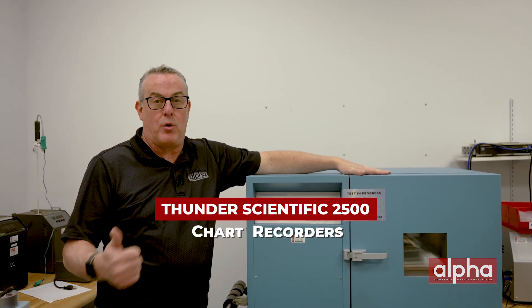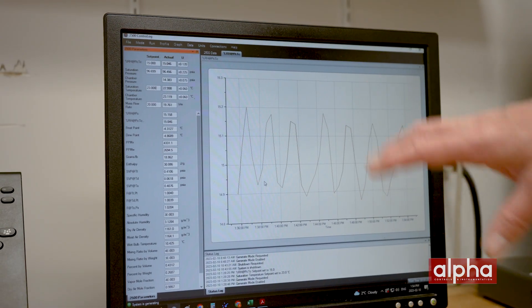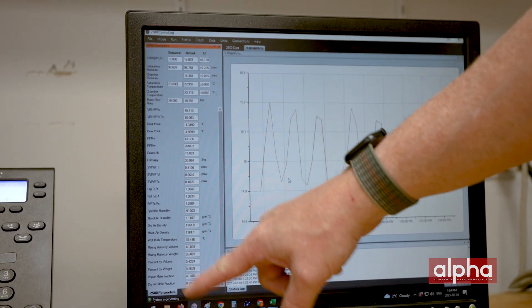You have the ability to do chart recorders, multiple probes, multiple data loggers — basically whatever you want. The chamber can be controlled by a software package called the 2500 ControLog. As you can see, it brings in a lot of automation and gives you all your psychrometric calculations on the side.